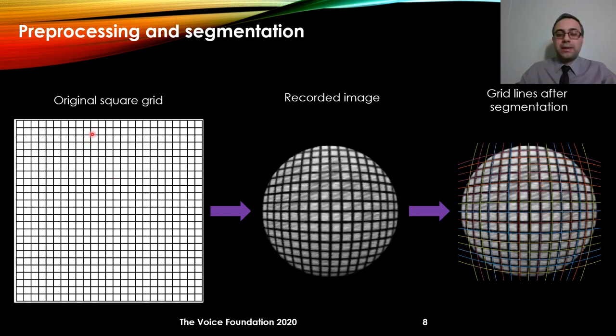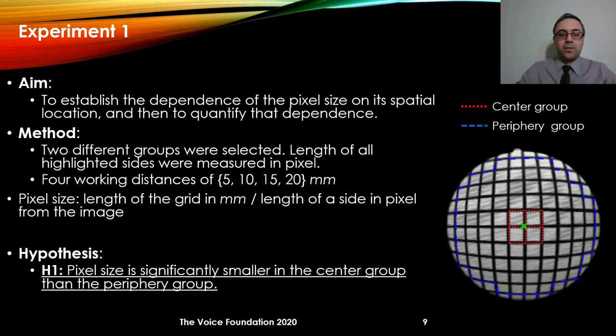In the original image we see that all of the lines are parallel to each other. However, in the final image after segmentation, we see that the parallel lines are becoming bent and bowed, and they are no longer parallel with each other. The aim of experiment one was to establish the dependence of pixel size on its spatial location and to quantify that. For this experiment we created two different groups: one group corresponded to blocks in the center, and the other to blocks on the periphery. We ran the experiment for four different working distances of 5, 10, 15, and 20 millimeters.